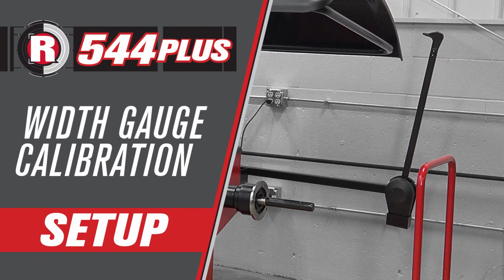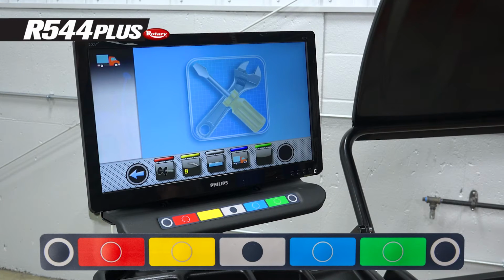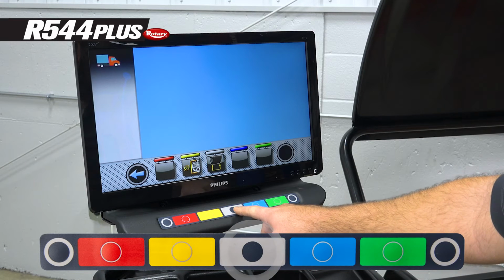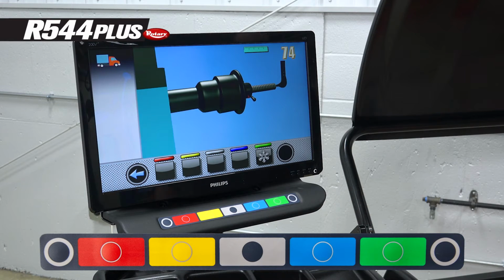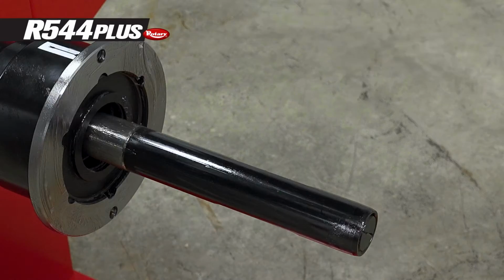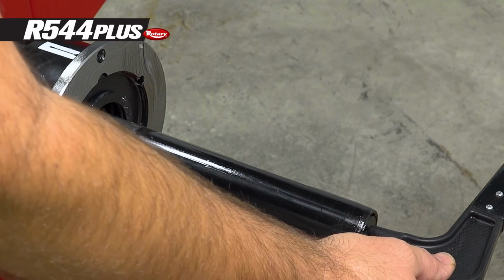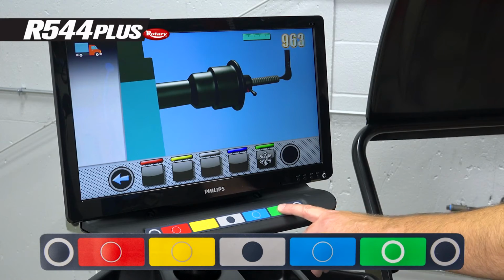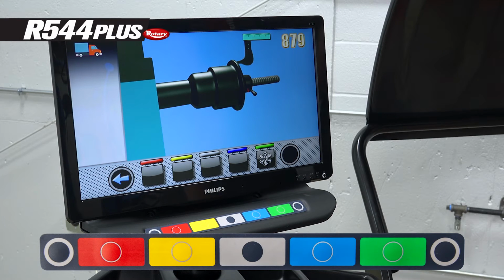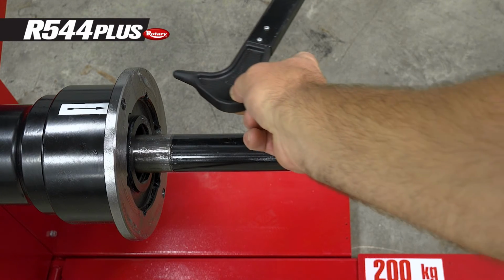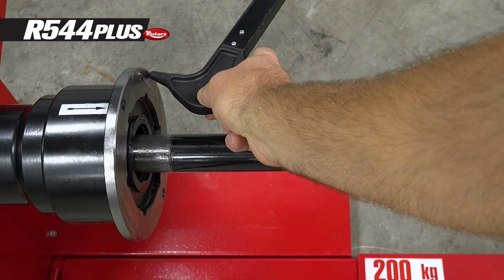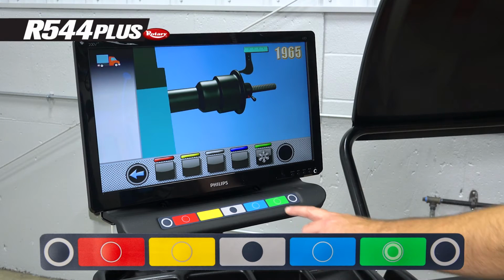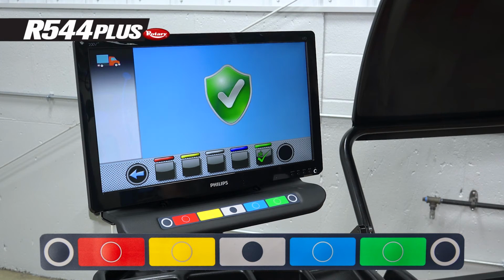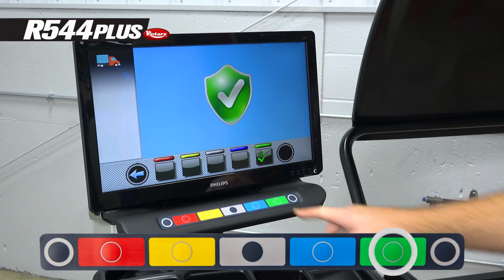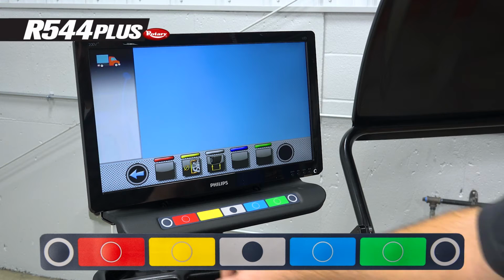Width gauge calibration. To calibrate the width gauge, press the gray button 2 times. Then take the width gauge and touch it to the end of the shaft. Now press the green button for the snowflake icon. Next, move the gauge to the front face of the hub and press the green button again for the snowflake icon. Once the check mark shows on the screen, press the green button to complete. Then press the back button.